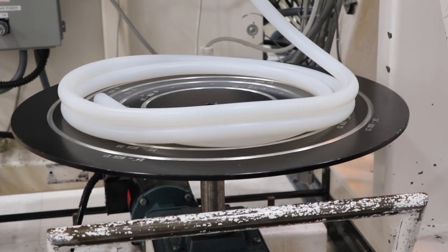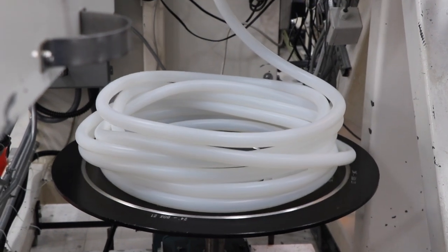This is very important in all aspects, from having a correct size ID. So when you're doing drug delivery, you're getting the amount of medication that you think you're getting, as well as from a concentricity standpoint. If your wall thickness is off, you're not getting proper occlusion of the tubing in the pump, and you could be dosing less or more medication to the patient than is needed.